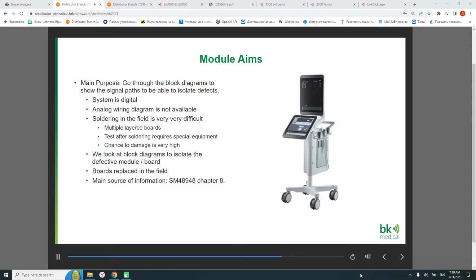Then it's possible for you to make a replacement of that defective board in the field. And we would say that this is a more professional take for you. So you can just go to your customer, exchange the part that you need to exchange, make an electrical safety test if needed, and then you're out again and the scanner is up and running. The main source of information for this training is Section 8 in the service manual.